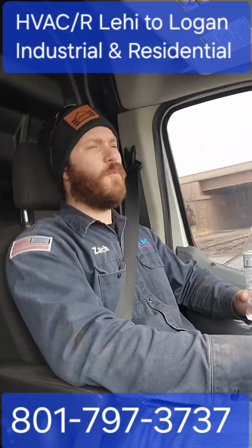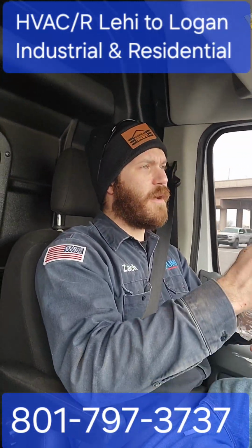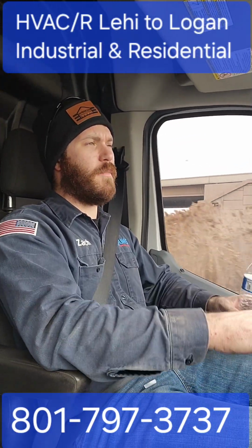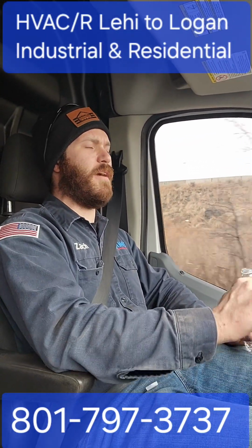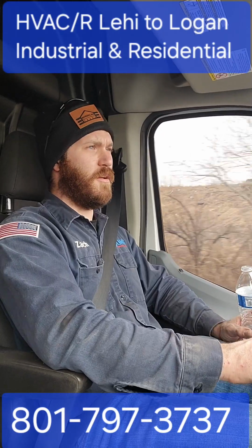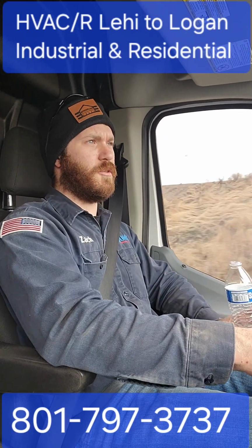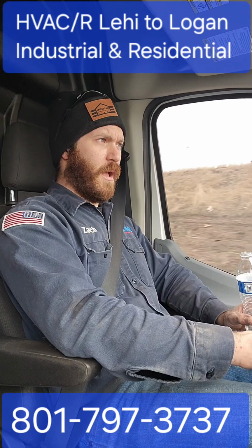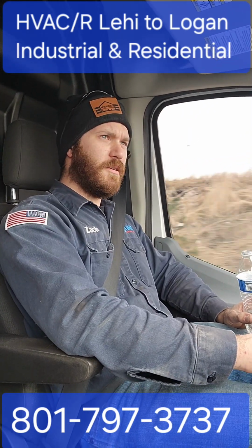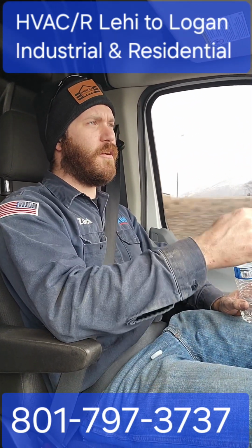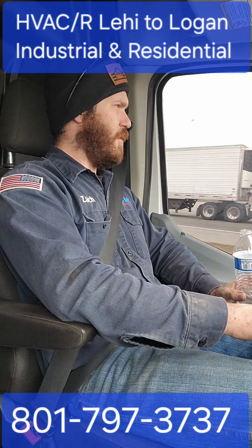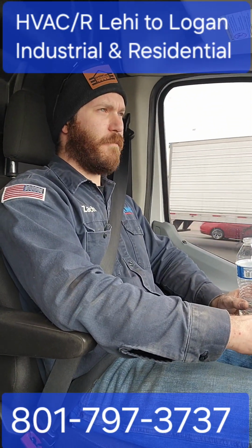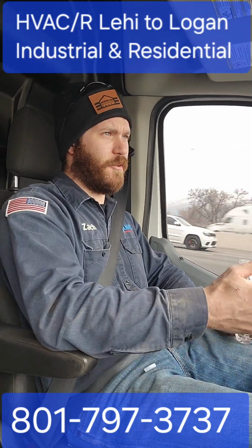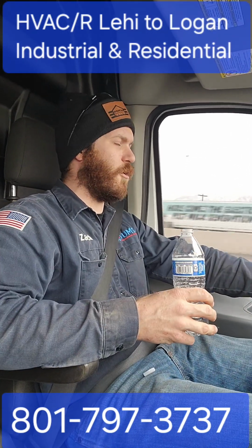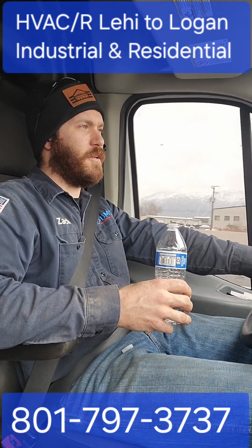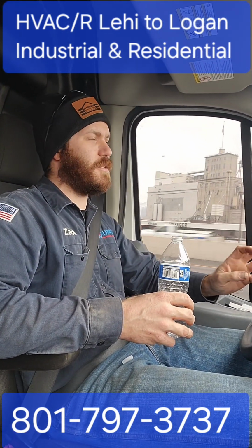And so it takes a couple more tries, but I've got my meter on there, I've got everything jumped out, and I've got my meter on this pressure switch, and I watch it happen. After a couple of tries, the inducer fan kicks on, but the pressure switch did not close. I said, that's strange. So I got a real long, skinny screwdriver in there and kind of manipulated the diaphragm on the pressure switch, and I was able to get the furnace to reliably light, I don't know, 10 more times in a row, which was more than I had gotten it to do previously. But I got it to relight 10 times in a row.